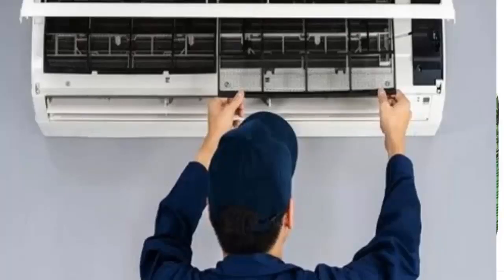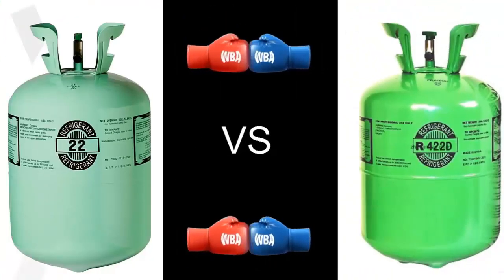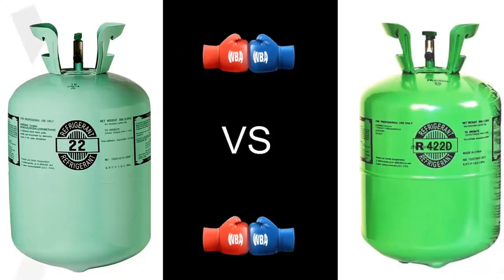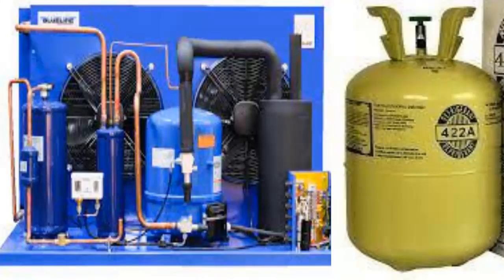Within the R422 family, the most recommended gas to replace R22 in air conditioning systems is R422D. Additionally, in lower temperature applications, the R422A refrigerant is widely used as a substitute for R22.